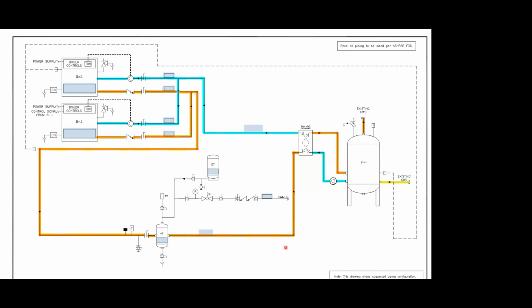Just a quick flow schematic of that. So again, hot boiler water is coming into one side of our heat exchanger and back to the boiler plant. It's chemical laden. Our boilers aren't designed for direct domestic water. And over here we have a storage tank with a dedicated pump that is simply picking up heat through our heat exchanger and bringing it back to the storage tank. That works great if you're trying to multi-use your boilers for both building heat as well as a domestic priority.